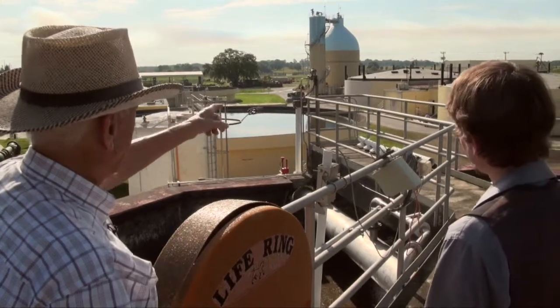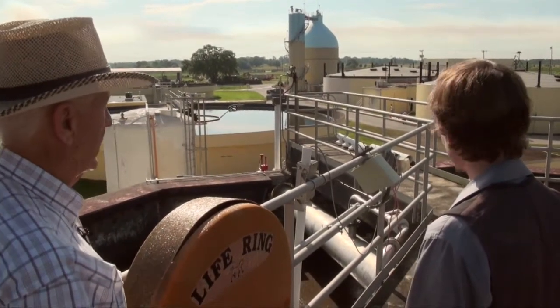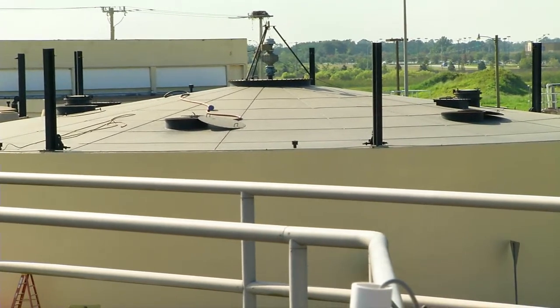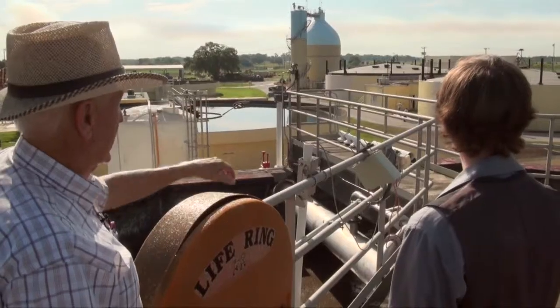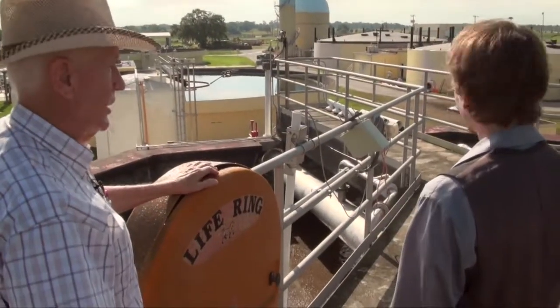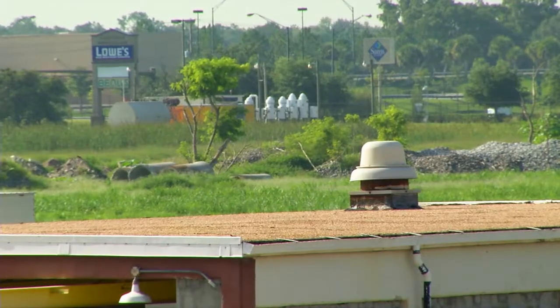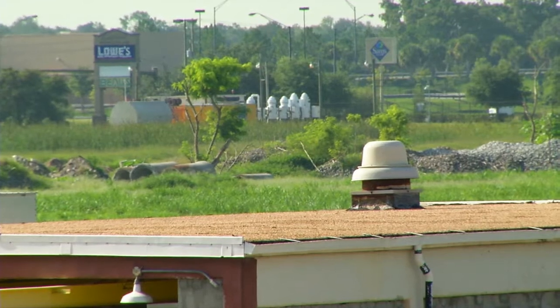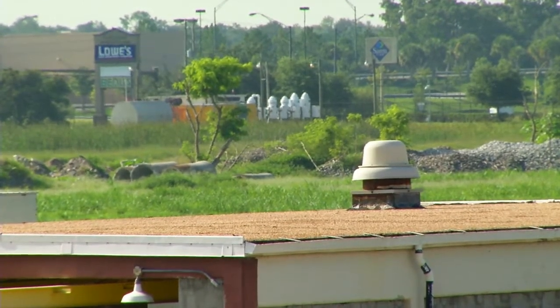Okay. Then it comes over to these large tanks, you see I'm painting one of them right now. Those tanks are called mesophilic. That runs at about 98 degrees, 99 in that area, about like our body temperature. Then in the back, the large building is our thickening system. That's where we thicken the sludge that comes from these tanks we're standing on. And then to the right further, way down in the field, across from that building, you'll see what looks like 6 white pumps. That's our final pump station that pumps it all 16 miles down to the wetlands treatment system.